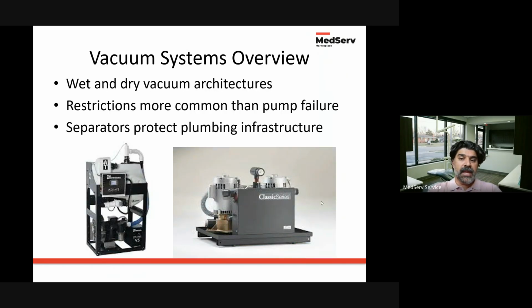Vacuums create negative pressure, and they are usually implemented in two ways. There's a wet vacuum and a dry vacuum. A wet vacuum, as it may sound, uses water to create negative pressure, and that requires water coming in from the facility to help create that pressure. So you'll have water coming in, and there'll be a turbine running and drawing it out. The dry vacuums create similar negative pressure, but without leveraging any sort of liquid. They're typically quieter. I think nowadays dry vacuums are a little more prominent in newer facilities, but that doesn't mean you won't come across wet vacuums in a lot of older clinics.